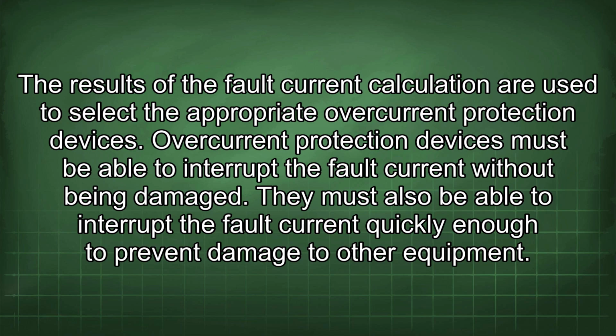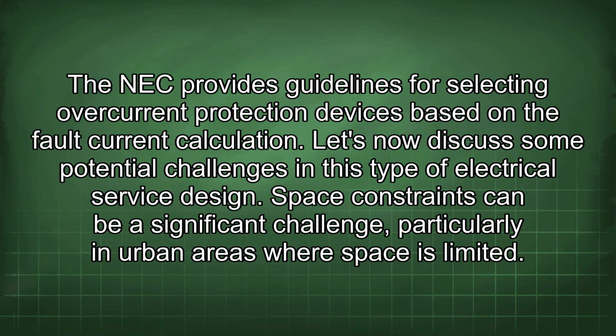Overcurrent protection devices must be able to interrupt the fault current without being damaged. They must also be able to interrupt the fault current quickly enough to prevent damage to other equipment. The NEC provides guidelines for selecting overcurrent protection devices based on the fault current calculation.